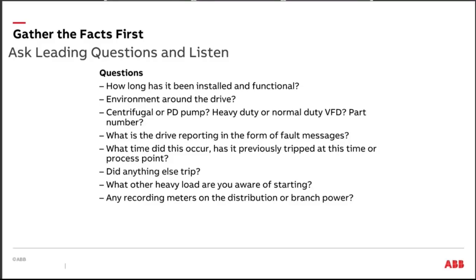I like to look at my actual application. If it's a pump, a lot of people are in a bad habit of using the word pump and they stop talking. Now, is it a centrifugal pump or is it a positive displacement pump? A centrifugal pump, something that goes roundy, is a variable torque application. I don't need a whole lot of current, basically hardly any current to move a variable torque load off of 0 speed. But if I'm a PD pump, a piston pump, positive displacement pump, then I need constant torque drives. I need 150% overload for 1 minute to get me up and running. So I like to know what kind of pump it is. That's very telling.